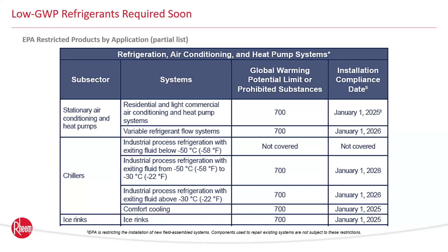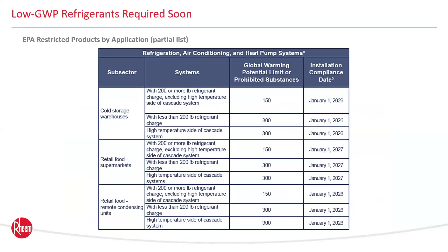The refrigerant alternatives below 700 GWP for air conditioning and heat pumps are primarily Class A2L refrigerants. Even more stringent EPA restrictions apply by application, requiring as low as 150 and 300 GWP in refrigeration applications in 2026 and 2027. Cold storage warehouses, supermarkets, and remote condensing units are all going to very low GWP limits in the near term.